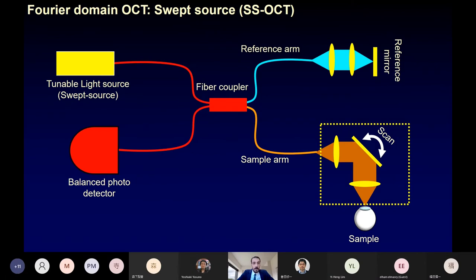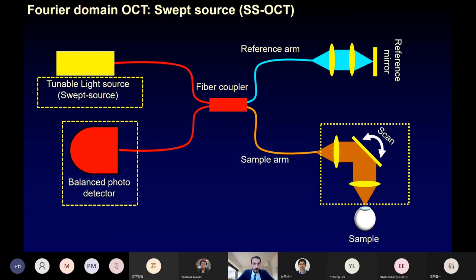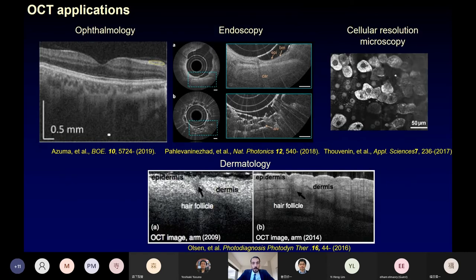The second variation of Fourier domain OCT is swept source OCT. The interference scheme and scanning is similar to spectral domain OCT, but the light source is tunable, where the wavelength sweeps along time, and signal detection is done using a photodetector. OCT has been widely used for clinical applications such as ophthalmology, endoscopy, cellular resolution microscopy, and dermatology.